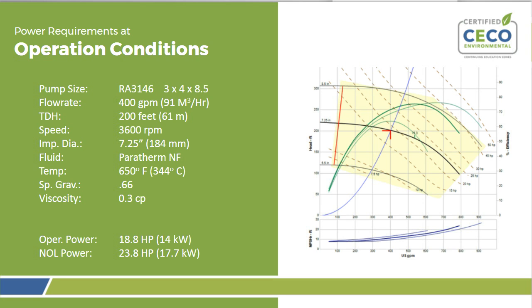But the problem comes in is that you're not starting this pump at operating conditions. At some point, this pump is going to be at ambient conditions. At some point, you have to start it up. There are some processes that are preheated, but those are not very common, and usually they require the pump to be operating in order to be preheated. So you have to consider, how am I going to start this pump, and what are the conditions when I do?